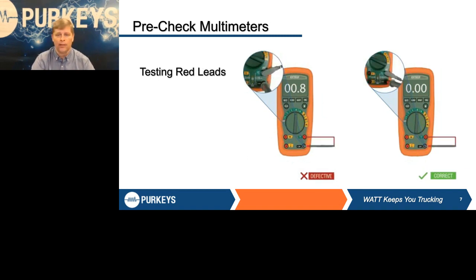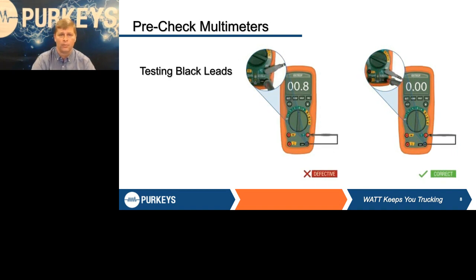We can now go back and check leads individually. Take the black lead out, leave the red one in, and use just the tip of the red lead to put it where the black lead should go, and check just that red lead. If it's bad, it tells you you've got to replace those leads. Take the red one out, do the same thing with the black lead. All we're trying to do is make sure that meter is right, not only the meter, but the leads, to get accurate readings. A difference in a little bit of resistance with a defective lead could very easily cause you to replace a good sensor, or check something inaccurately simply because it's picking up extra resistance.